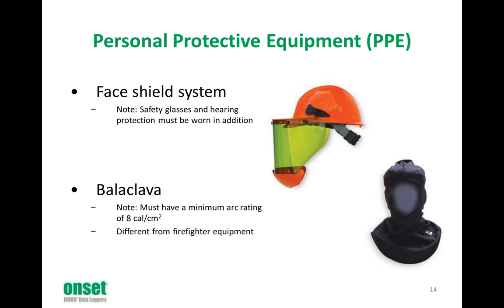So this is a typical face shield system. Note, in addition, you'll still need the safety glasses and hearing protection to be worn. Then you need a balaclava, and it has to have a minimum arc rating of 8 calories per square centimeter. And this is different from firefighter equipment.